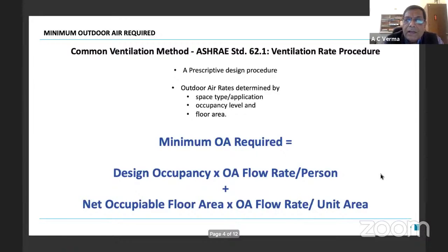The amount of outdoor air has been specified, which is worked out on the basis of your space type and application, occupancy level, and floor area. A very simple formula, which is shown here, is the design occupancy multiplied by the outdoor air flow rate per person, added to the net occupiable floor area and outdoor air flow rate per unit area. That is the basis on which we work out the minimum outdoor air required.